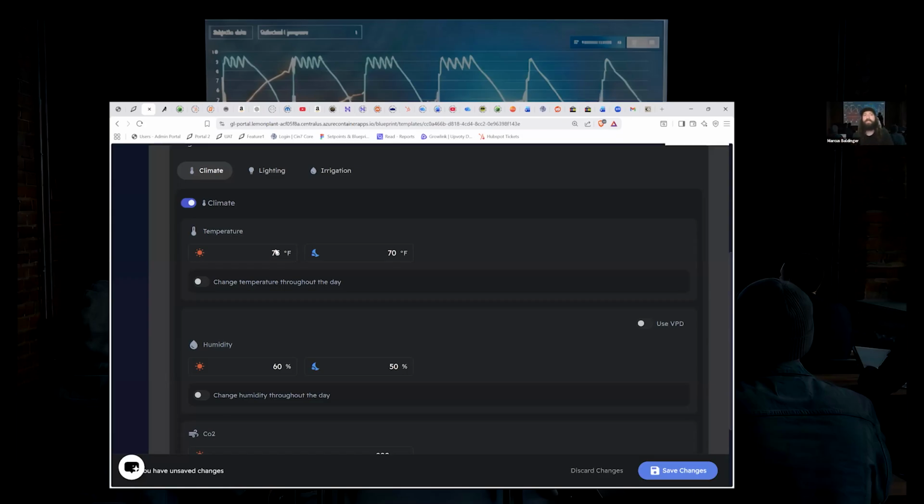What a blueprint is going to be is just the physical set point that those rules are going to be referencing. For example, if you wanted to have 75 degrees as your daytime singular set point, like you would in a normal dynamic rule, this is where it's pulling that data from. And conversely, if we change that on a day-to-day basis, it's going to update that so that the rules in your room can then pull from it.